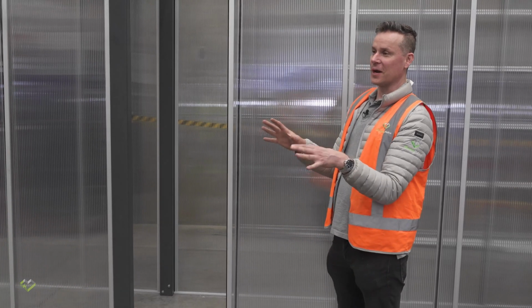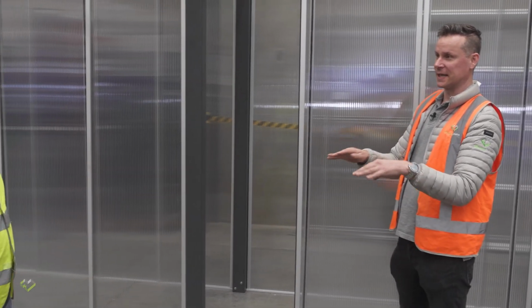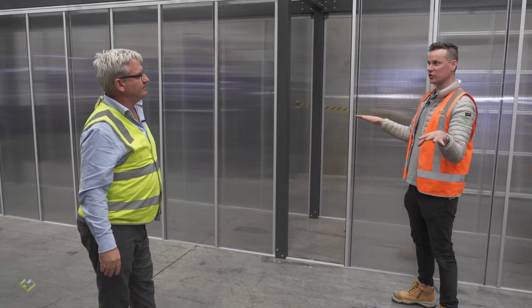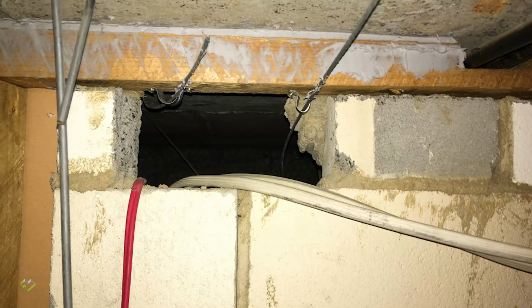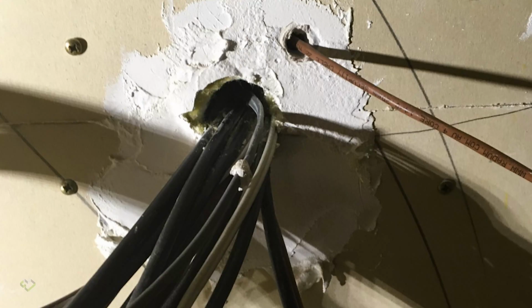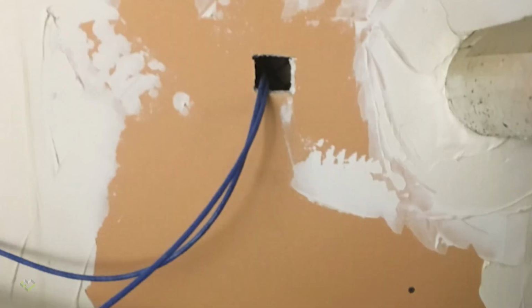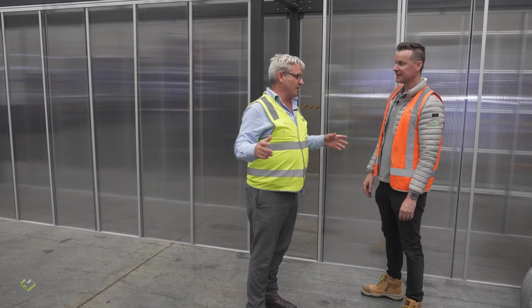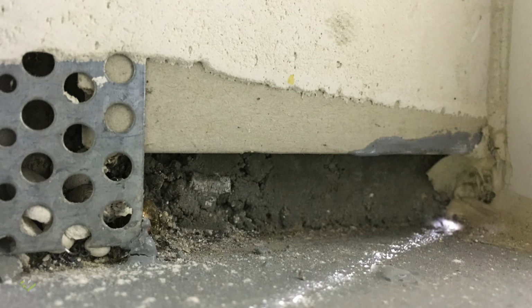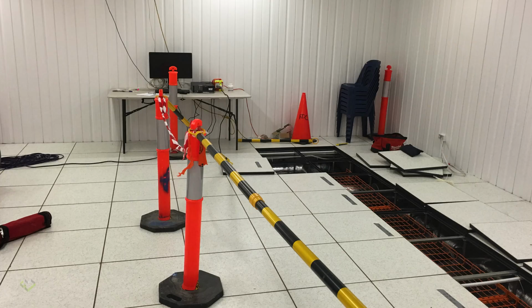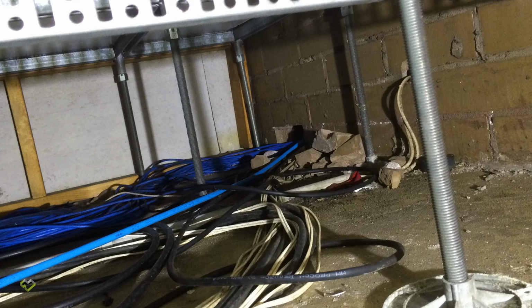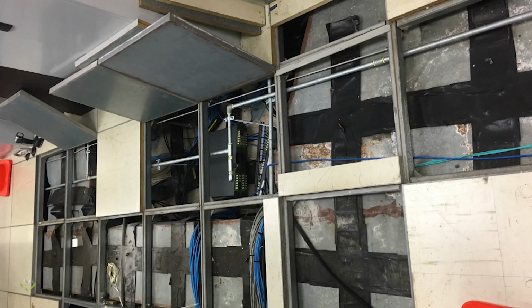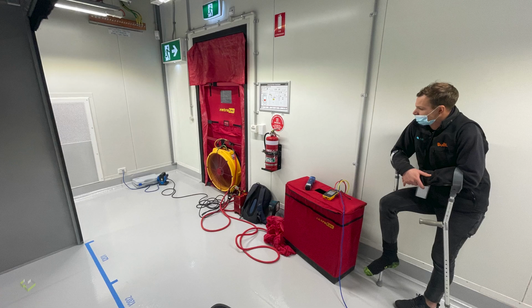One thing that I always notice with the false floor system is that over time they just end up with huge penetrations into other parts of the building, and a good lot of the air that you're pumping into the floor isn't actually making it to your racks. Yeah, that's right. That's called flat spots under your floor. All the analysis, sometimes you just can't get rid of that flat spot. And there's infrastructure under the floor which doesn't help as well. You've got cable baskets, you've got comms, you've got power baskets, you've got other infrastructure under the floor, so much cleaner to do it above floor.